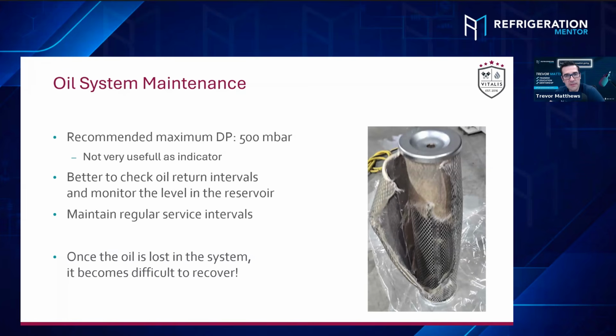Yeah, because there's a lot of dynamics when we talk about failures. I talk to a lot of people, and the design could be perfect, but if the install's bad, there's going to be an issue. The design can be perfect, the install can be perfect, but the commissioning can be terrible. The design could be perfect, the install could be perfect, the commissioning could be perfect, but the service is terrible. You know what I mean? Or then the maintenance. I do a lot of trainings right now on CO₂, where some customers don't want to pay for maintenance. So if you don't pay for maintenance, how are you going to prevent a compressor from failing, or something happening, losing product at the end of the day?